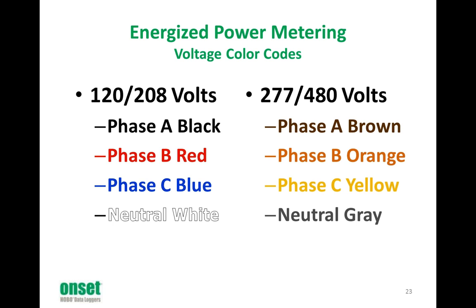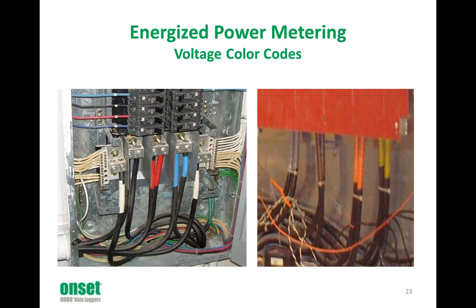And some of the conventional color coding here in the U.S. For small commercial electrical panels, 120, 208 volts, typical to average plug load, you're going to have the black, red, blue on your phase colors, and a white neutral conductor. When you get into the higher voltages, such as commercial lighting or large pieces of commercial equipment, you could run into 277, 480 volts. And those are usually marked with brown, orange, and yellow phase colors and a gray neutral wire. This is not always 100% the case, but it's pretty conventional in the U.S. And here's a few examples. On the left-hand side, we see a 120, 208 volt electrical panel. And then on the right-hand side, we see color coding for a 277, 480 panel.